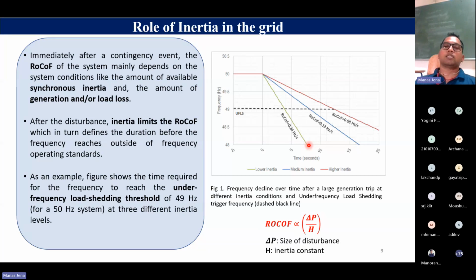So as I mentioned, inertia means resistance to change. If you have a higher inertia, you expect a lower rate of change of frequency compared to a system having a lower inertia. So you can see that for the same system, if your inertia is going down, you are expecting a higher RoCoF. RoCoF is proportional to the size of your disturbance, the contingency, upon H, the inertia constant. Higher is this value, lower will be the RoCoF.